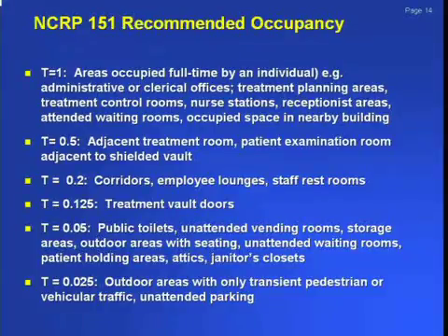In other words, you assume that your therapist is actually in that room no more than half the time when treatment is going on in the adjacent vault. Exam rooms, we use an occupancy of 0.5 also. For corridors, employee lounges, and staff restrooms, the occupancy is assumed to be 0.2.